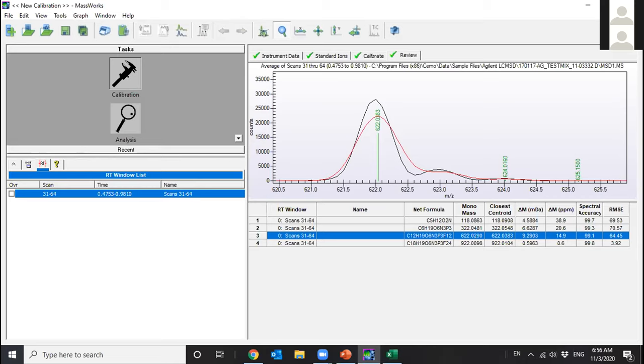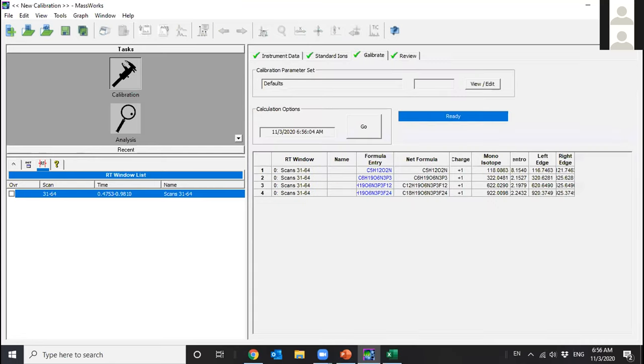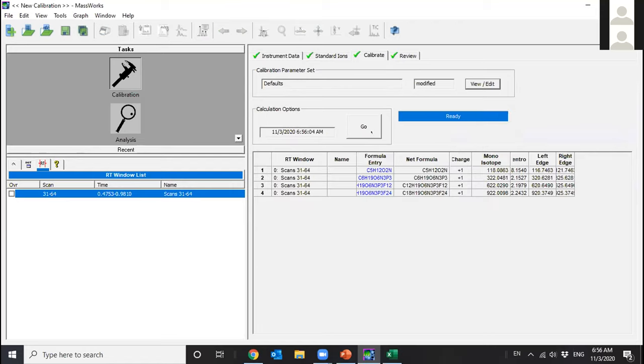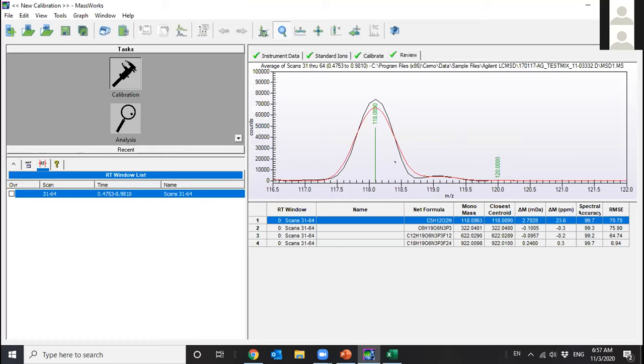And all you need to do is to go back to calibrate and view and edit and change the peak width to a narrower peak width of 20% wider instead of 30% wider after calibration. And then you say go, and then you take a look at the delta M, the mass recovery. They are all within 5 millidaltons. And take a look at the spectral accuracy, they are all 99 and above. So that's a satisfactory calibration.